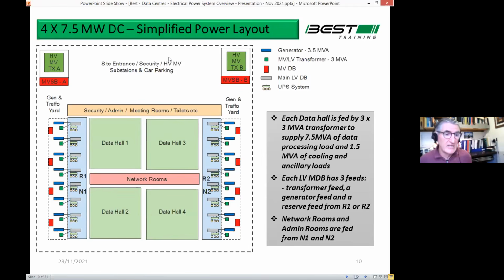At some sites, the substation is actually remote. The ESB bring cables from their substation into the site. So that's what I'm showing here. You see the 2 transformers, the A transformer and the B transformer, which transform from HV to MV. And then you have your MV switchboard shown in red. You have your A board and your B board. You'll start getting a feel for it very shortly. Everything is duplicated or has a spare reserve system backup.